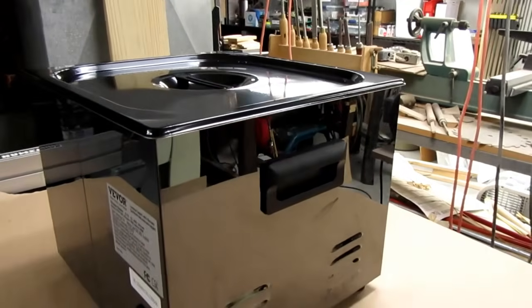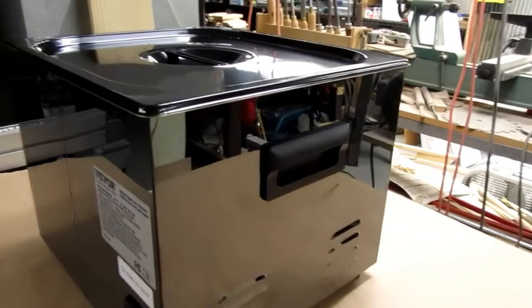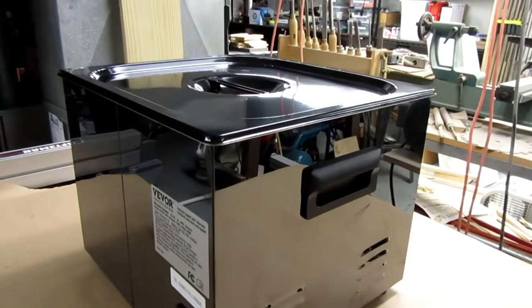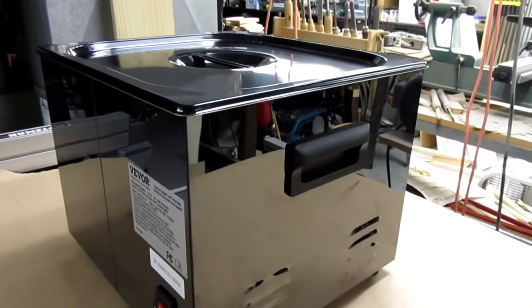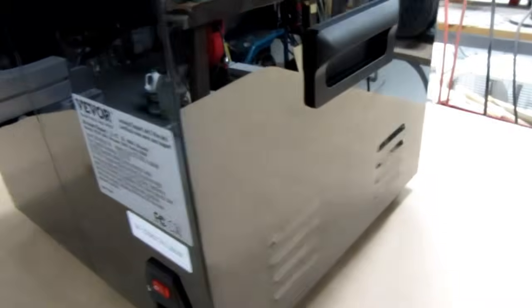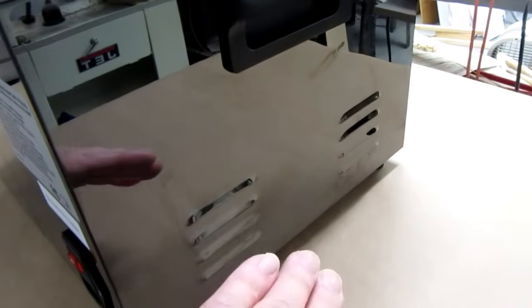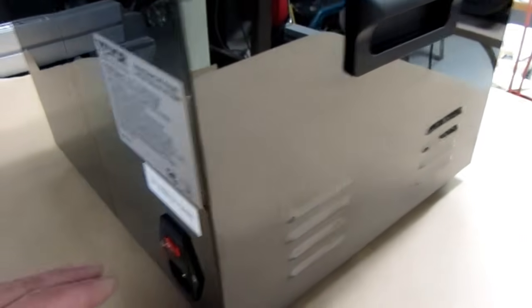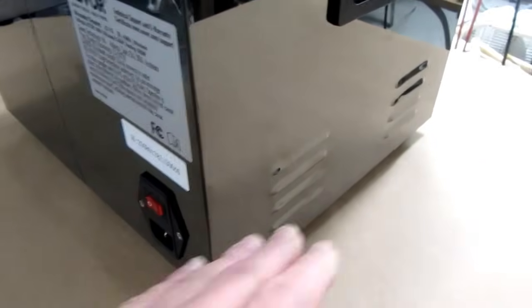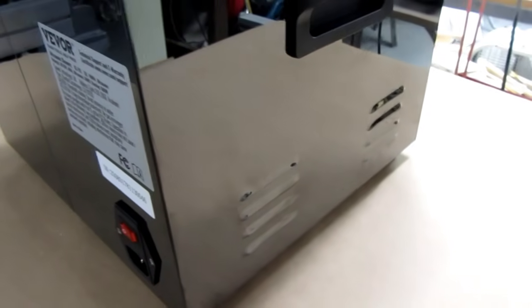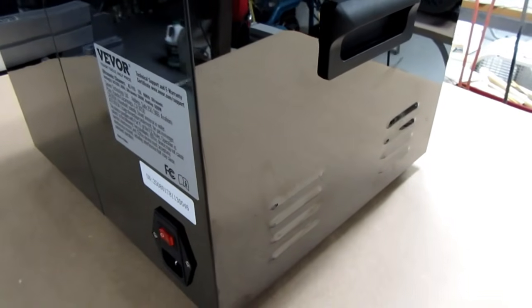Although, and this is a critical point, these less expensive models, the non-industrial models, are not water sealed. There's air vents here and here, and a big air vent on the bottom with a cooling fan. Lots of places for water to get in and reach the electronics, which are all sitting on the bottom panel in here - that'll fry these units if you get water inside of them.